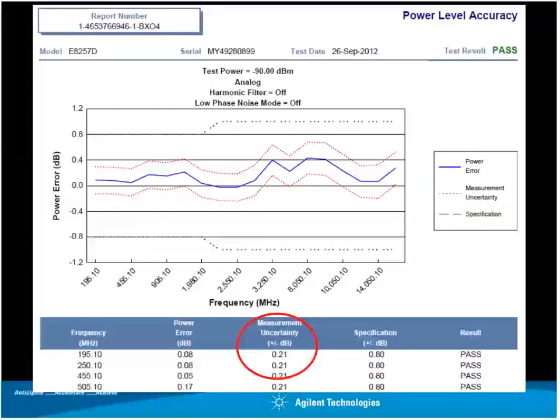Perhaps more important in this report, as always, the most important part is the data. And as Trevor was just telling you, when you see an accreditation body symbol on there, you should have every reason to expect to see the measurement uncertainty, again, per the Guide 98, the ISO GUM. And so I've just circled it in red on this particular slide, and you can also see it up above in the chart as well. So you may or may not see a chart, but you should certainly expect to see the tabular measurement uncertainty when you are receiving a report which includes an accreditation body symbol.